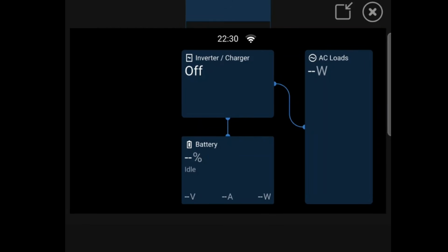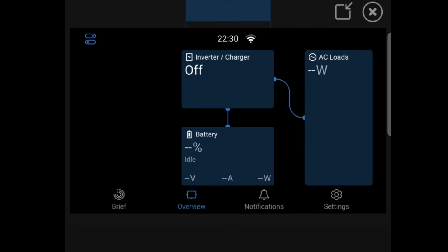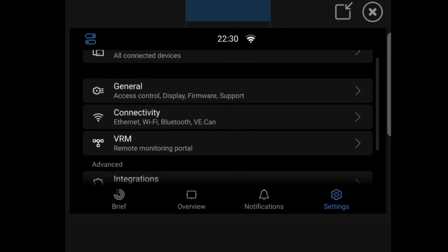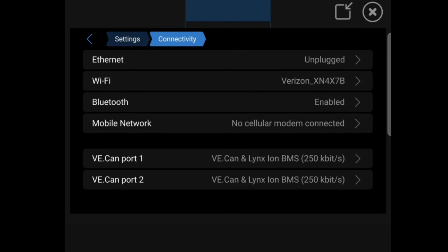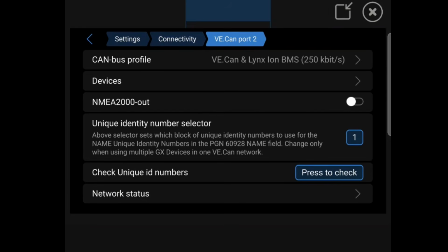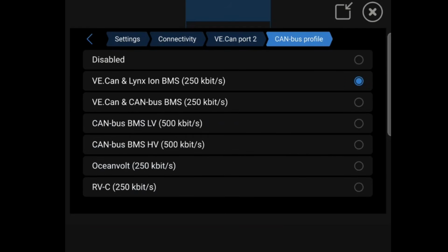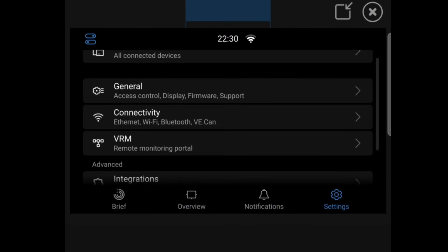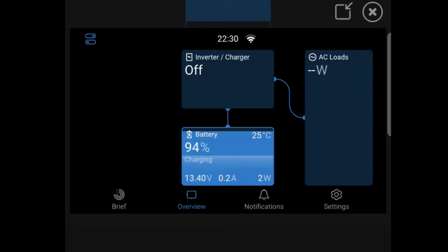We have the connections made, but there's still no battery information on the bottom tile. We need to set the VE.CAN port speed so we can get information from the Epoch BMS to the Cerbo system. So tap the screen, hit settings, go to connectivity, VE.CAN port 2 is what I'm using, and it says CAN bus profile at the top. Hit the arrow and select CAN bus BMS LV 500 kilobits per second. Click that, go back to the overview, and now we have battery information.